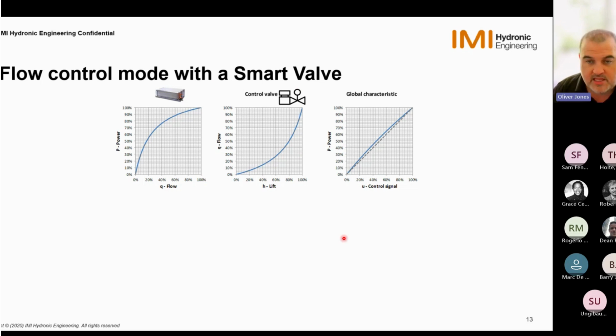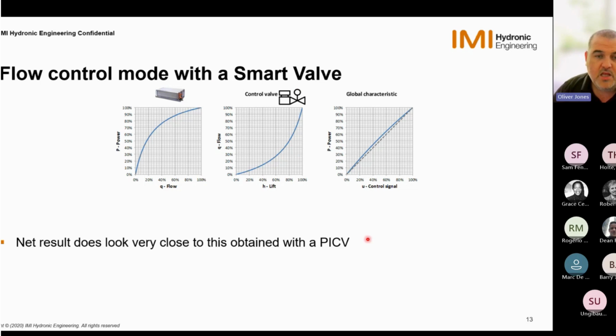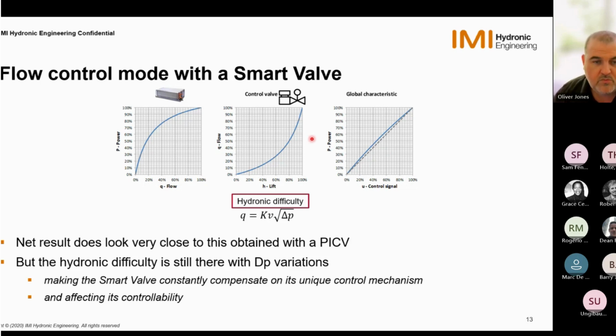Because of what's happening in the black box of the smart valve, we now are getting this final curve, which when combined to the terminal unit, gives us this global circuit characteristic that is quite good. So the hydronic difficulty is still there, and the smart valve must constantly compensate on the unique control mechanism it has, and that affects its controllability.